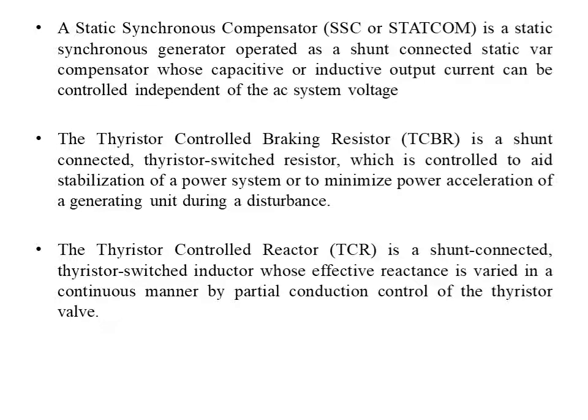Thyristor controlled reactor is a shunt connected thyristor switched inductor whose effective reactance is varied in a continuous manner by partial conduction control of the thyristor valve. So it consists of a bank. By switching the bank, we can inject reactive power into the system, or we can absorb reactive power from the system. This is nothing but an inductive bank, and by controlling or switching this inductive bank, we can control the power flow.